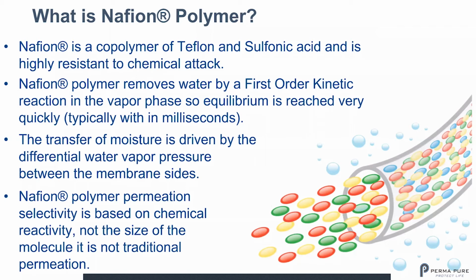Okay, and so it's also not traditional permeation. With traditional permeation, it's kind of like a bug screen, where you have a screen with holes in it, and the holes match the size of the molecules that you want to move through the screen. That's not what Nafion does, because the water actually becomes part of the material's chemical structure. Because of this, no energy is required. It just works on a differential vapor pressure, and it's highly efficient, and it happens very quickly.